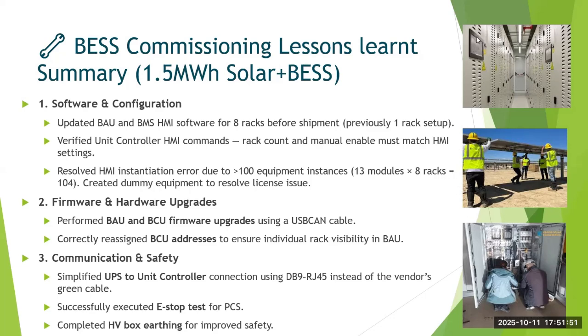As you can see on the right hand side, there will be a local HMI user interface, which will be used to understand the BESS. But the software they provided for us was only for 3 racks. It was not for 8 racks. So again, at the site, I had to go and commission, upgrade this BAU's BMS HMI software. And again, the commands to operate the BESS with respect to racks were not enabled. So again, I had to enable those.